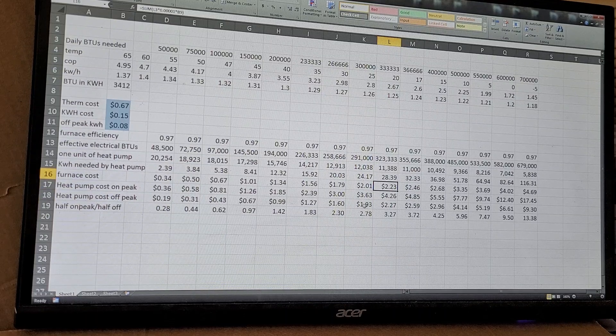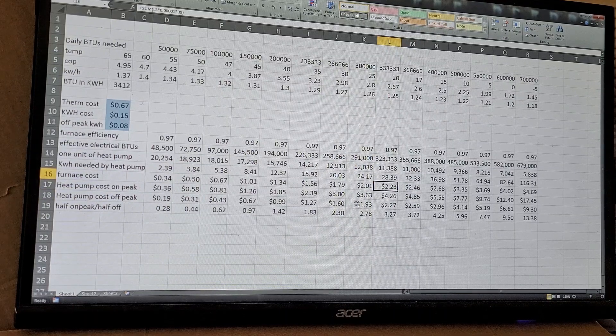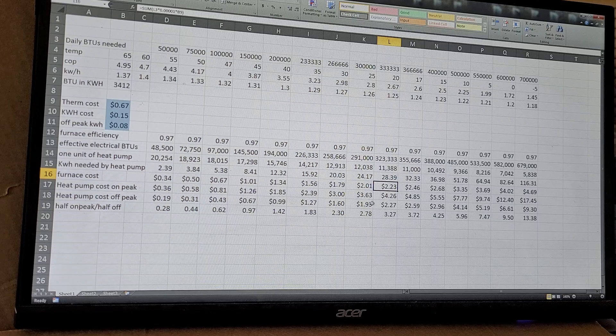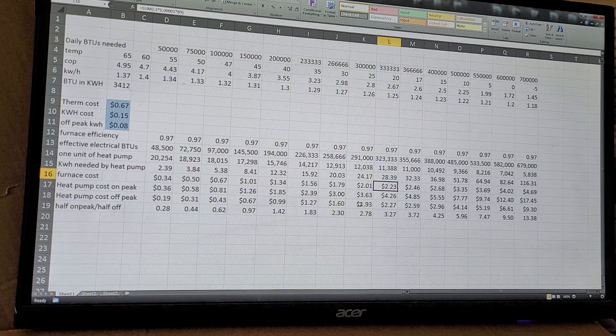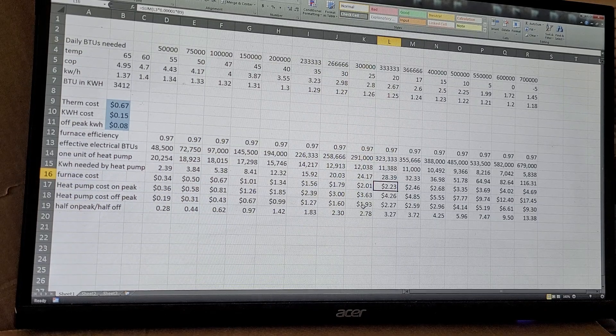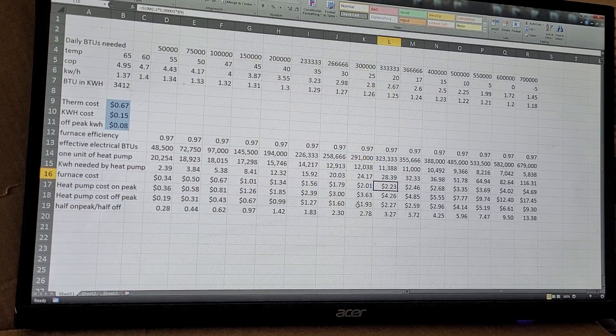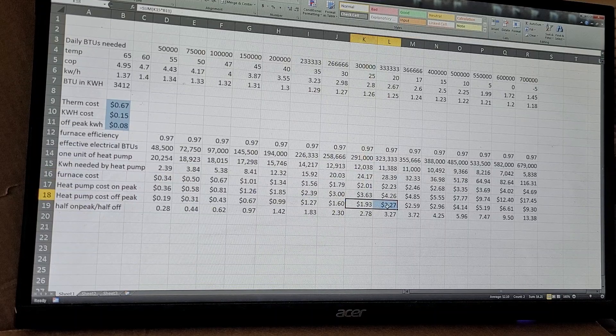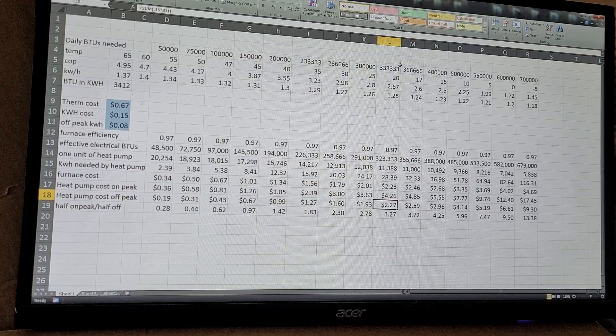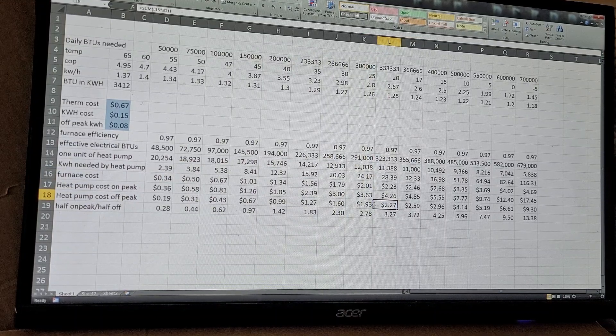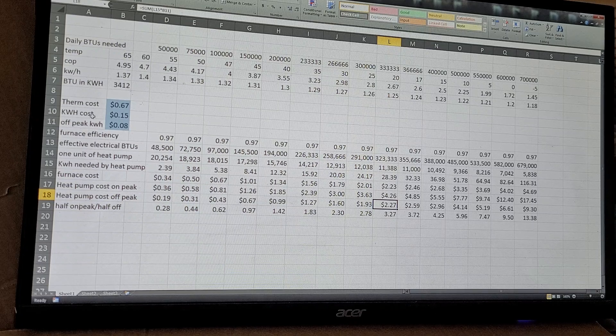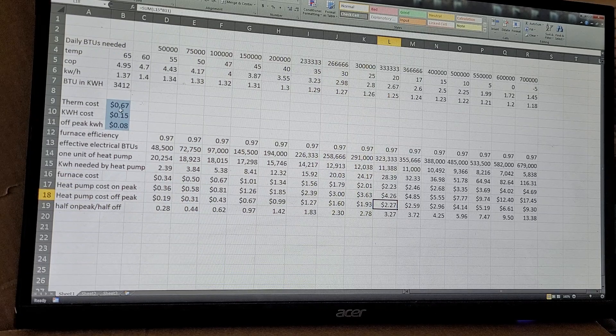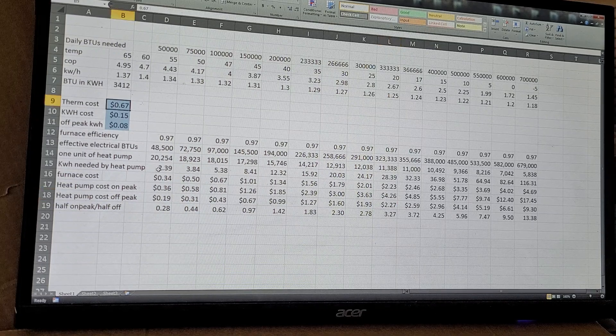But at 20 degrees it's more expensive to run the heat pump than the furnace. So somewhere your break-off is 22 degrees. If you have a good enough thermostat you might be able to just have it monitor the outside temperature and your on and off-peak, and then just switch over to the furnace when it gets below 20 degrees. But that really depends on what you're paying for electric and the gas rates.